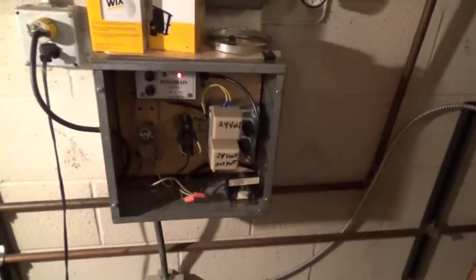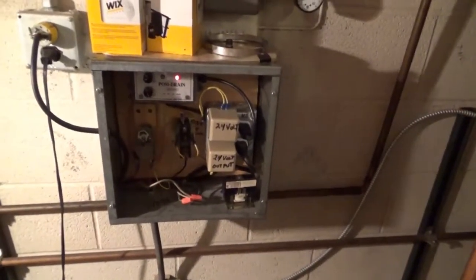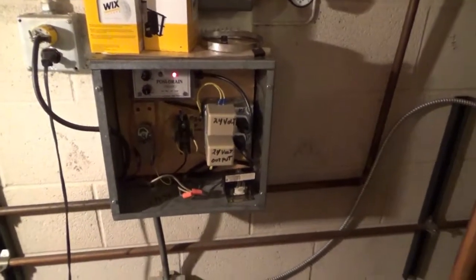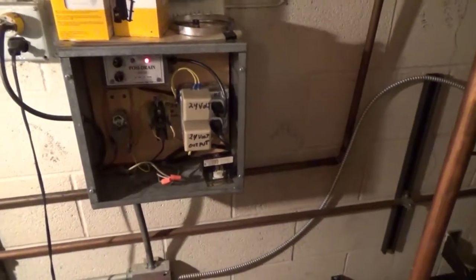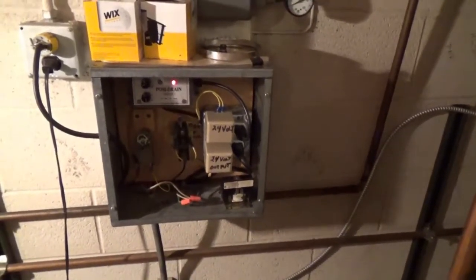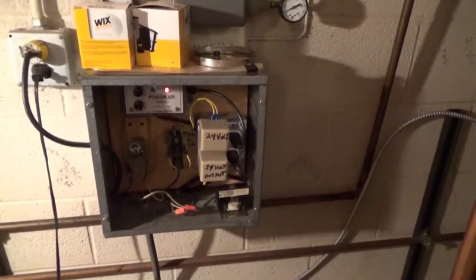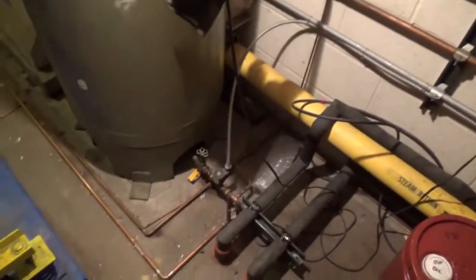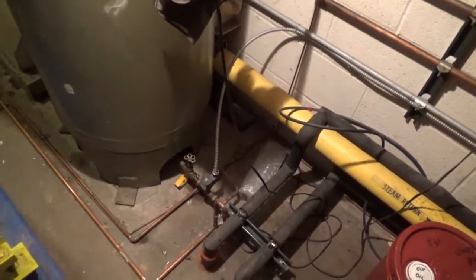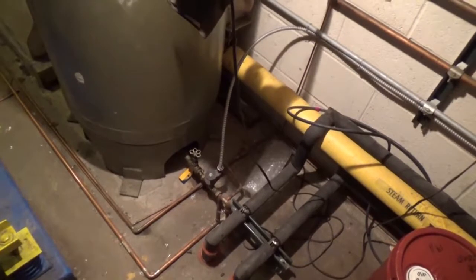This box here, George put together. George worked at IDS for years and years. He was actually here a little bit before the building was even completed. What this system here does is operate a valve on the bottom of the air storage tank, and every hour or so this valve will open up and let the air blow out of the bottom of the tank for 2 to 3 seconds. When that air blows out the bottom of the tank, it just removes any excess water or moisture that's in there.